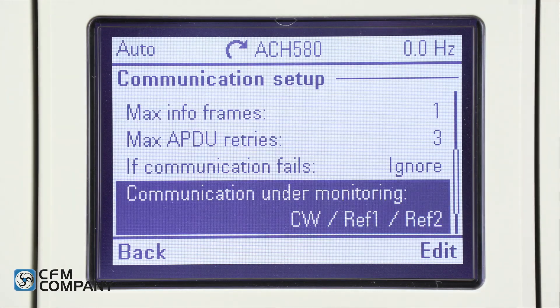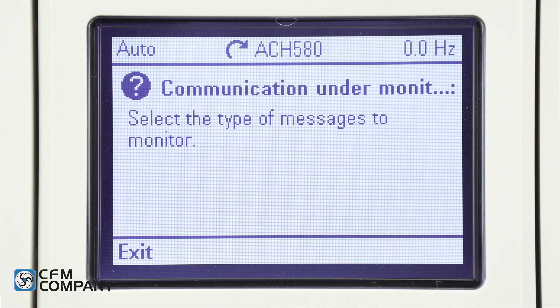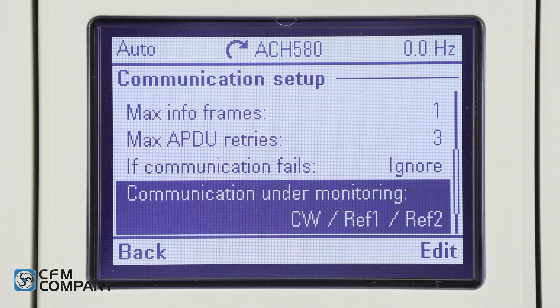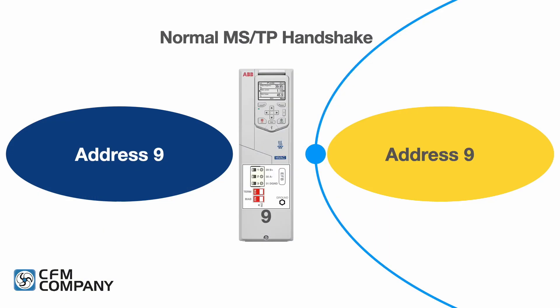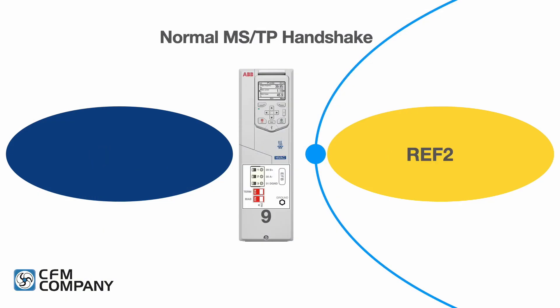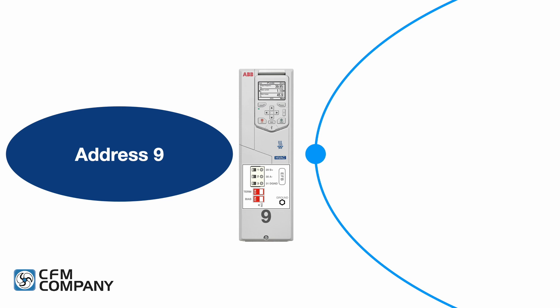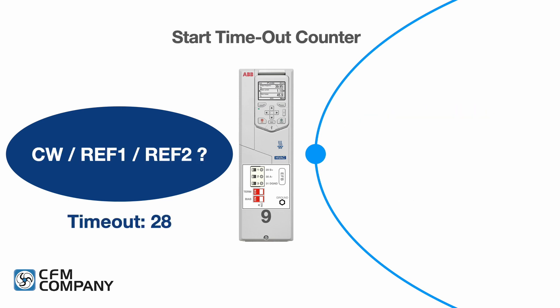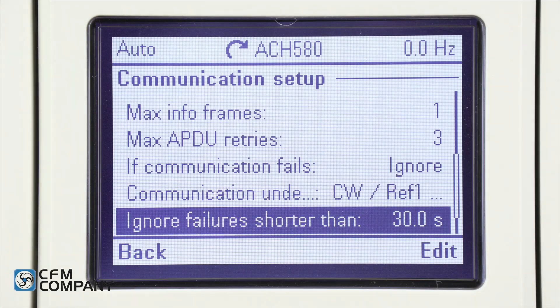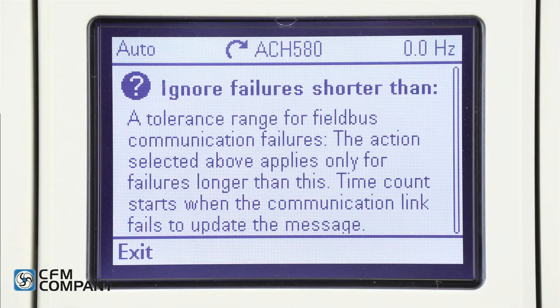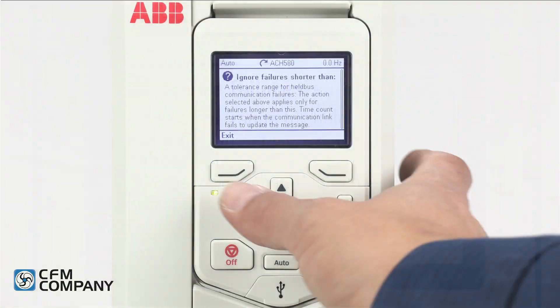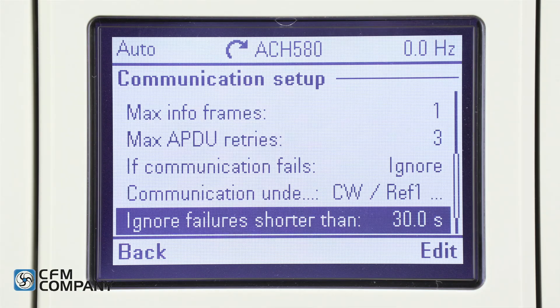Next is communication under monitoring. Press the question mark button — select the type of messages to monitor. Press exit. Leave this at the default value of CW/Ref1/Ref2. With this selected, the drive is going to watch the command word, the reference one word, and the reference two word. If at any time one of these three words is not received, the timeout counter will start. Next is ignore failures shorter than. Press the question mark button — this is the tolerance range for field bus communication failures; the action selected above applies only for failures longer than this. The time count starts when the communication link fails to update the message. Press exit and leave this at the default value of 30 seconds.